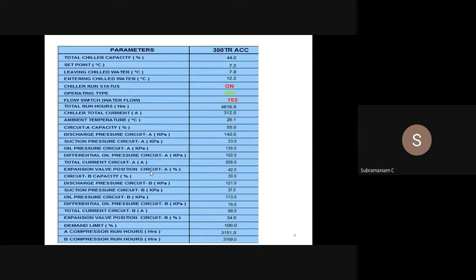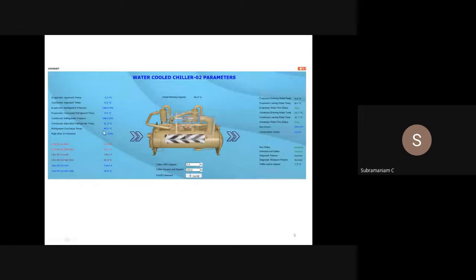You get all this information from the equipment to the BMS screen, and this is how the graphics will look like. This is how the entire parameters also are going to look like. And from here you can change the set point, chilled water set point, on/off demand command, and current limit set point also you can change from here.